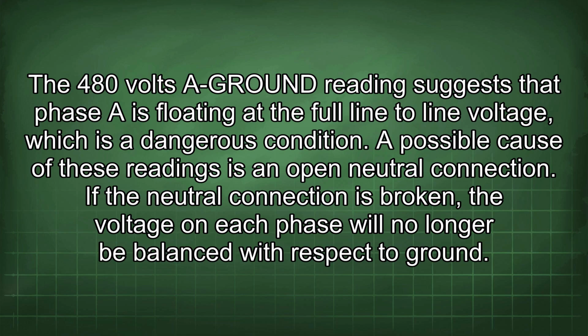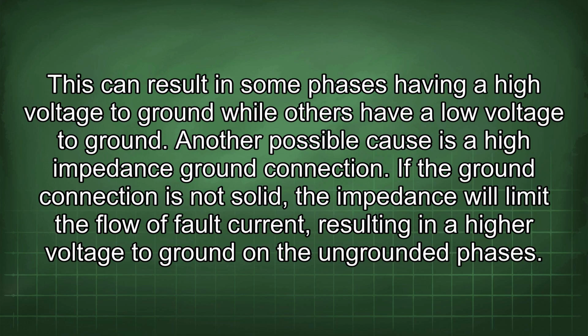If the neutral connection is broken, the voltage on each phase will no longer be balanced with respect to ground. This can result in some phases having a high voltage to ground while others have a low voltage to ground. Another possible cause is a high impedance ground connection. If the ground connection is not solid, the impedance will limit the flow of fault current, resulting in a higher voltage to ground in the ungrounded phases.